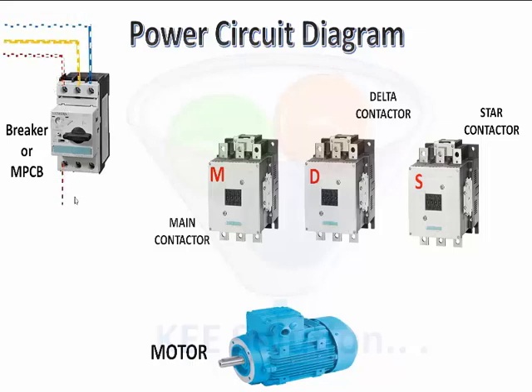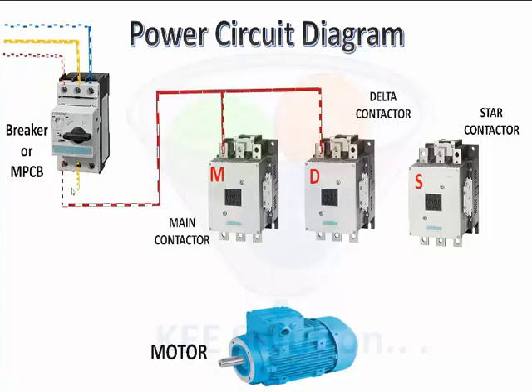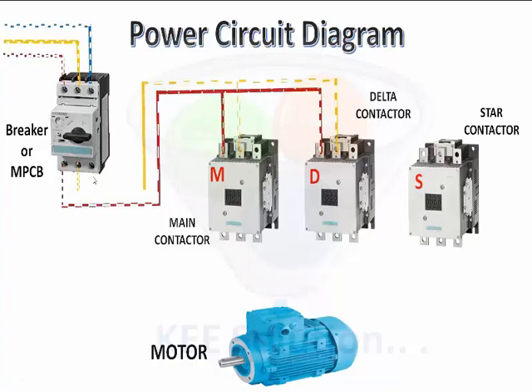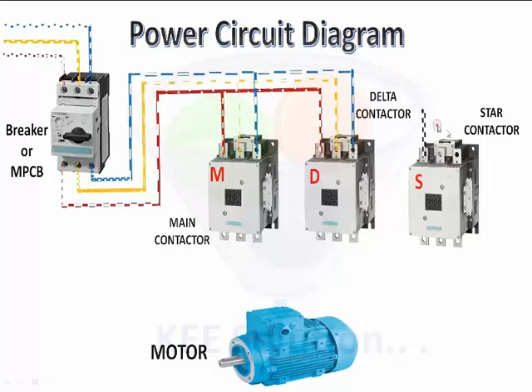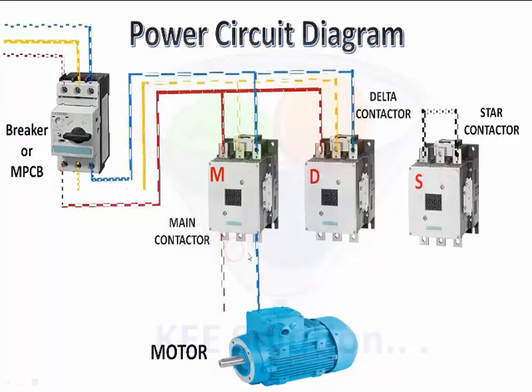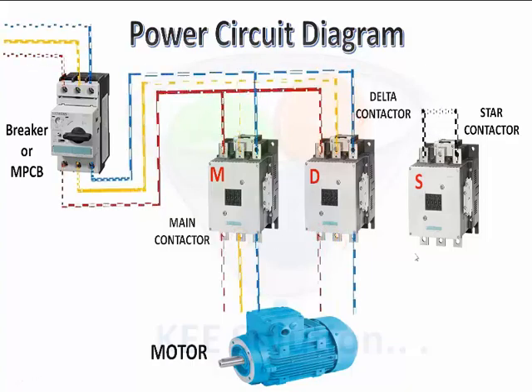First we take the red phase. Red phase should be connected at the first terminal of the main contactor and delta contactor. Yellow phase similarly at the second terminal of the main and delta contactor, and the third phase in the same way. In the main contactor at the end terminal, red, yellow, blue phase in sequence, and delta similar to the main contactor.